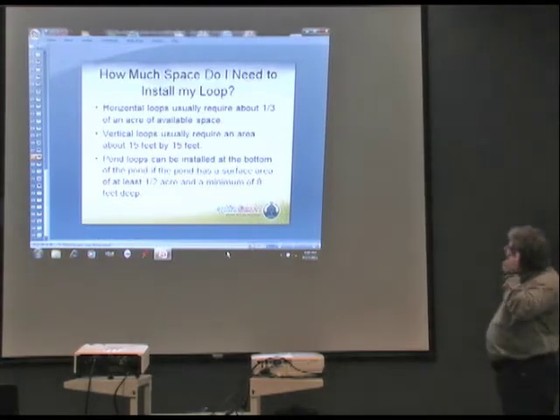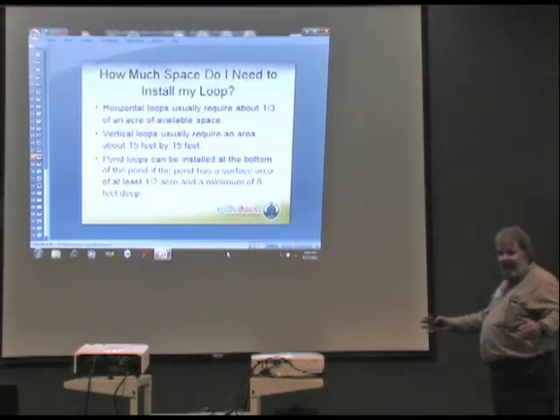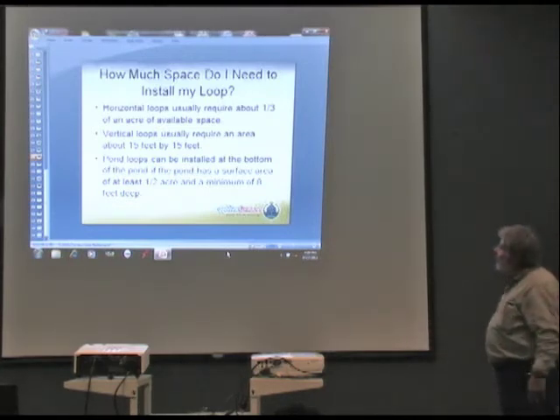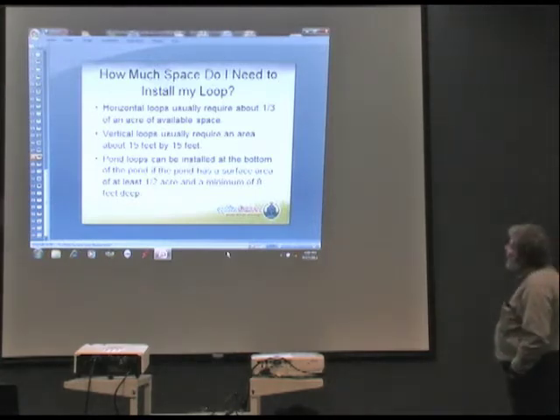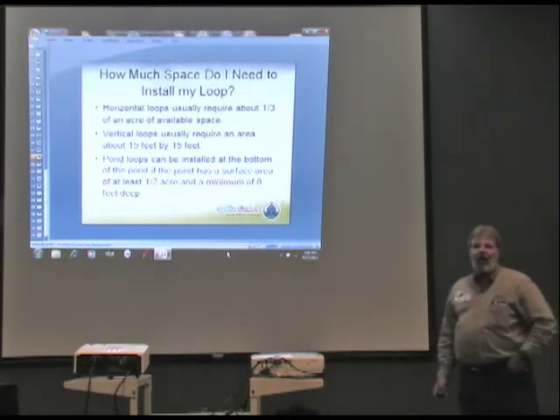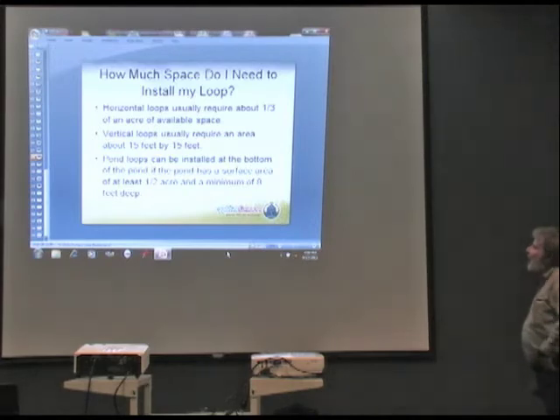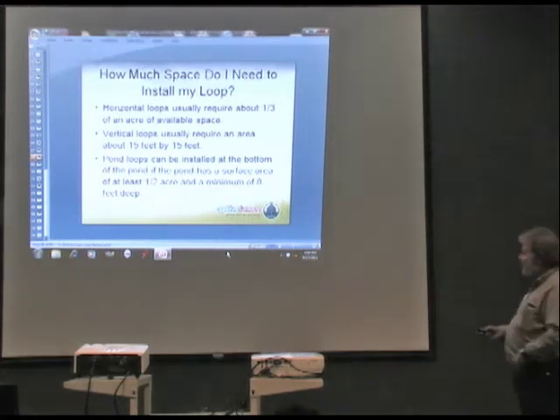Vertical loops require an area about 15 by 15, so we get separation. The pond loops, it's got to be at least a half an acre, and we need about 8 foot deep. We can get horizontal on a lot of lots. We need to stay away from your water lines and stay away from your septic because we will freeze them in the winter. So we need to stay like 3 feet away from those, which is not a big deal.